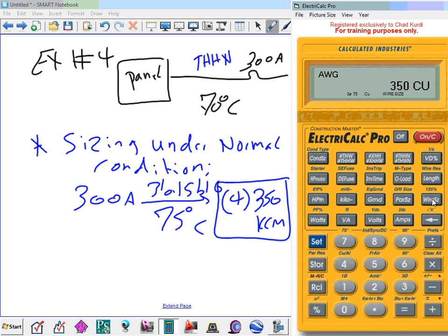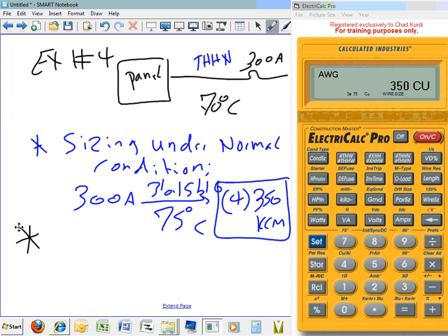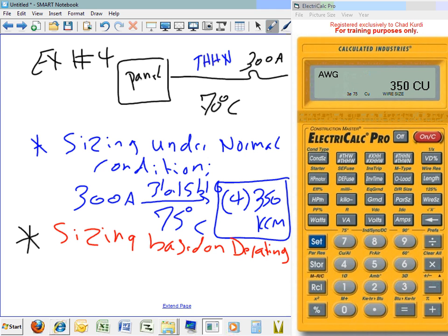Okay, so let's do the second one, sizing based on the derating. So no matter what, you can't go lower than 350 because that's what we size normally. Based on this one, guys, what's my load? 300. Okay, my temperature is 70. That's a heck of a hot. What's the derating factor for 70 under the 90-degree column? You're going to go to 310.15(B)(2)(a), 70. Everybody came up with 0.58.